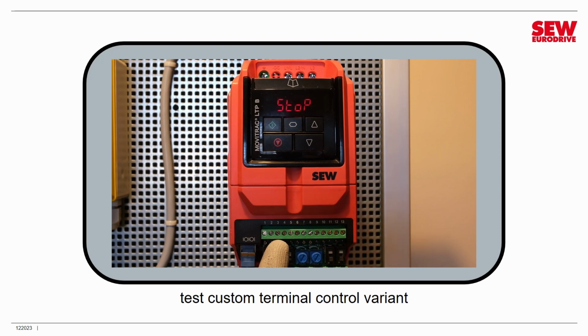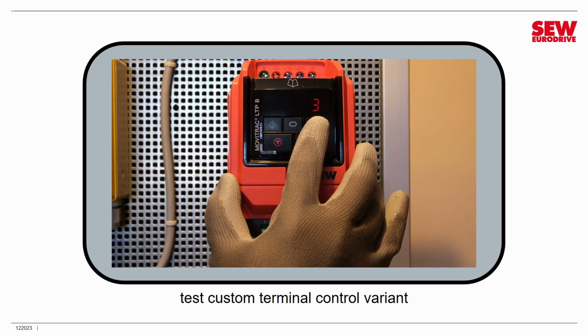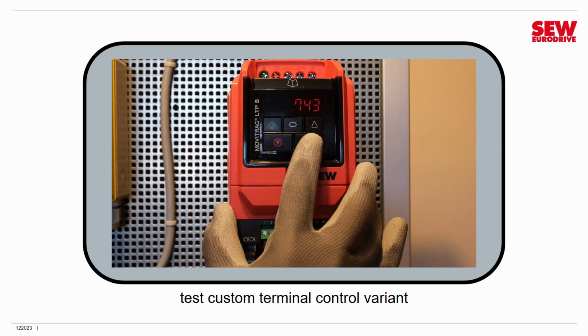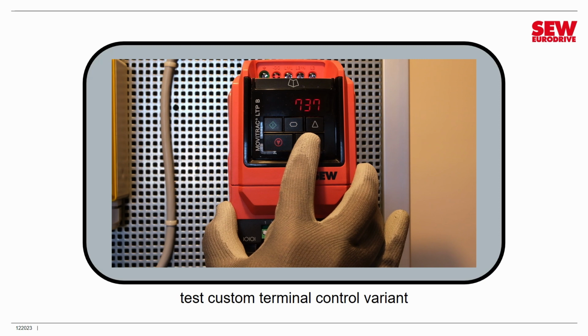Let's turn digital input 2 on to pick our second. That's the keypad. Re-enable the VFD, and I'll press the up button on the keypad, and you can see it's controlling the drive now. Let's decelerate back down. So that's our second speed source.